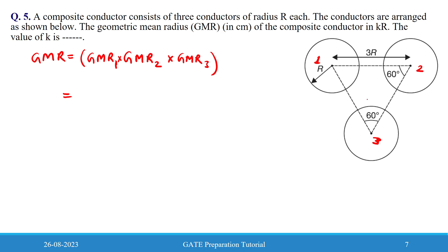So GMR will be GMR1 multiplied by GMR2 multiplied by GMR3, all to the power 1 by 3. Suppose this is the first conductor, then the second and third. If you see, all conductors have symmetrical spacing, so all have the same GMR. Unlike the previous question, where there was unsymmetrical spacing, so the conductors did not have the same GMR. Symmetrical spacing means GMR1 equals GMR2 equals GMR3, so the whole GMR will be GMR1. If we calculate the GMR for one conductor, we get the GMR of the whole composite conductor.